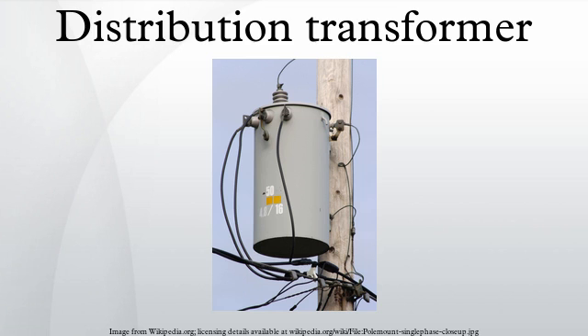This type of distribution system, called grounded Y, is preferred because the transformers present unbalanced loads on the line, causing currents in the neutral wire. With the delta connection, this can cause variations in the voltages on the three-phase wires. If no neutral wire is available, a delta or phase-to-phase transformer must be used. This has two bushings on top connected to two of the three primary wires, so the voltage across the primary winding is the phase-to-phase voltage. This type is used on long distribution lines where it is uneconomical to run a fourth neutral wire.